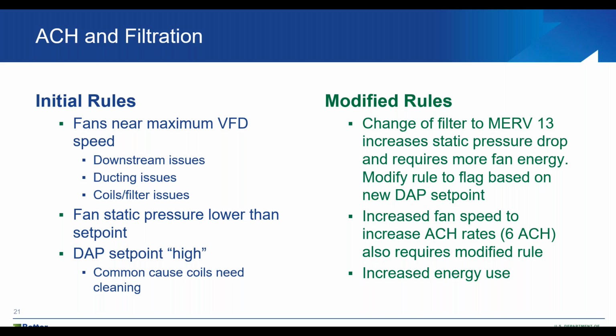Are these issues from coils not being cleaned? I once saw a pressure drop in an air handler of over 4 inches or higher due to lack of maintenance. The coils were in such bad shape that they decided to just replace them. The system went from three air handling units operating near capacity to two air handling units with the third as a backup, which was part of the original design. So as part of the FDD original rules, that would be found.